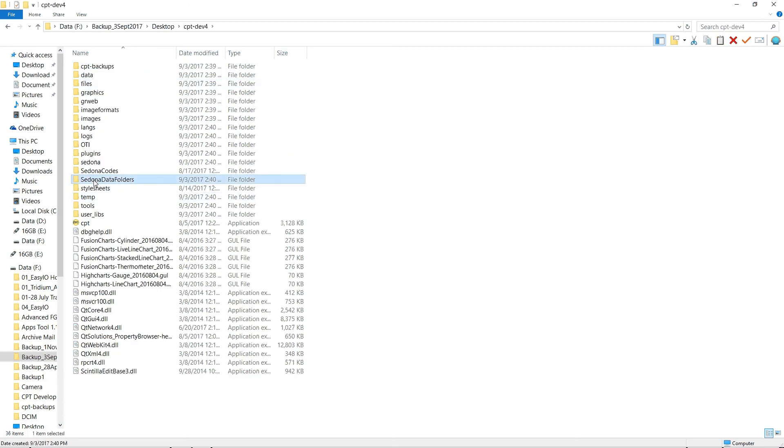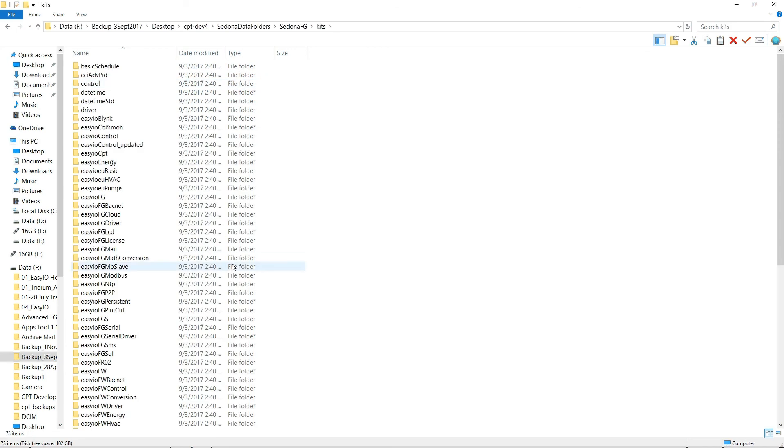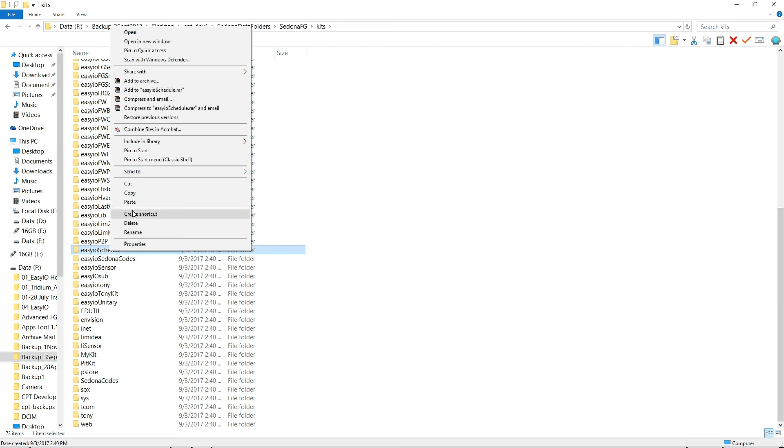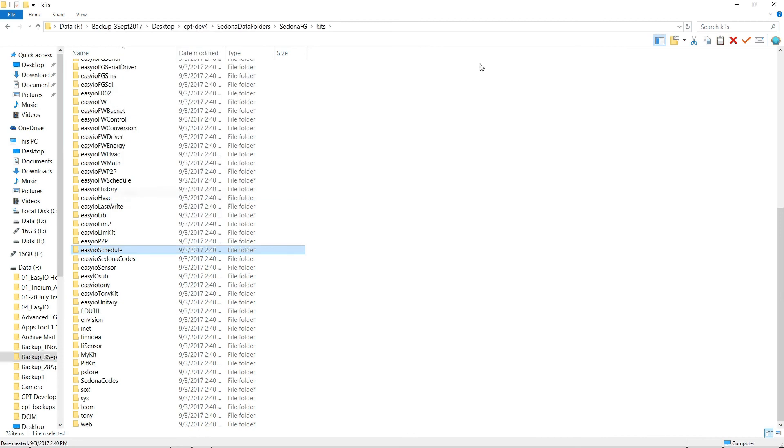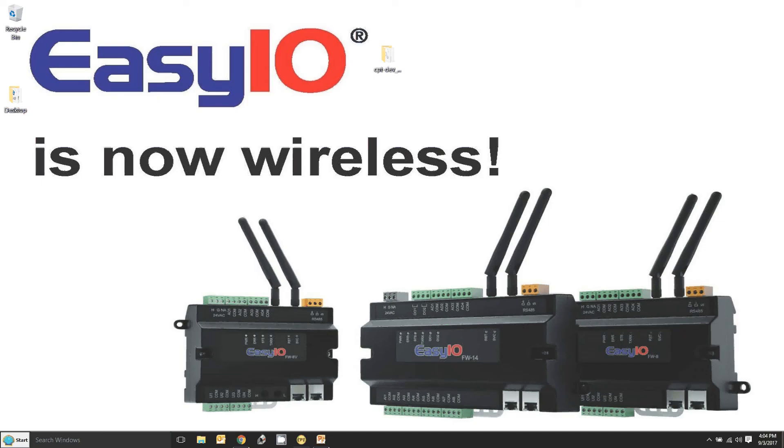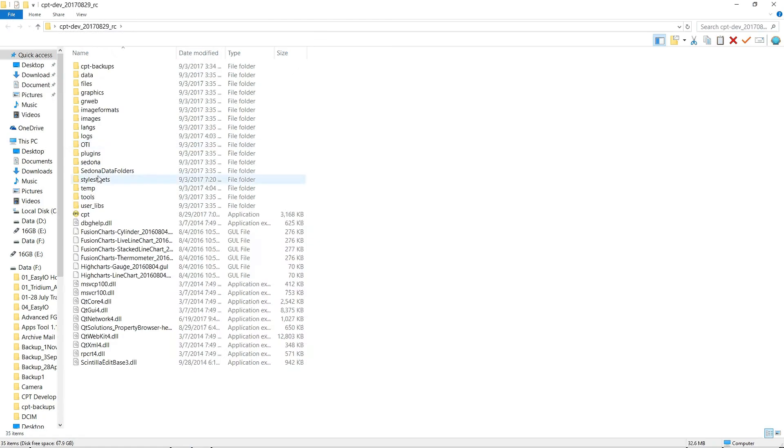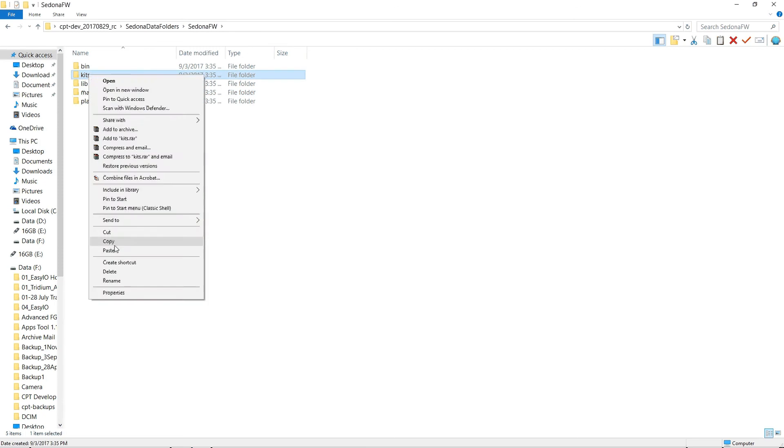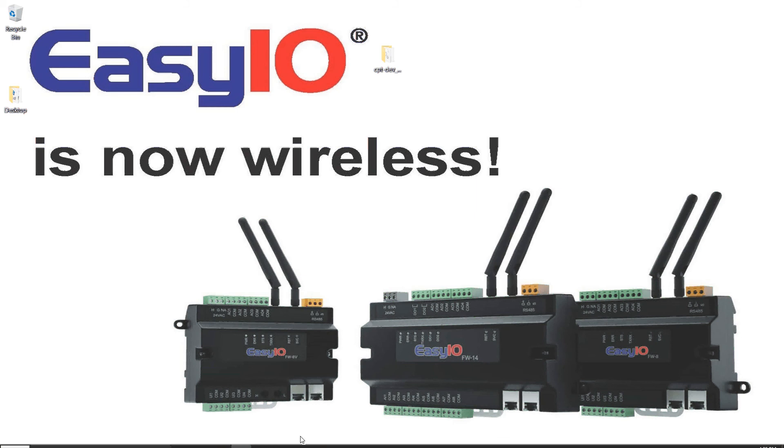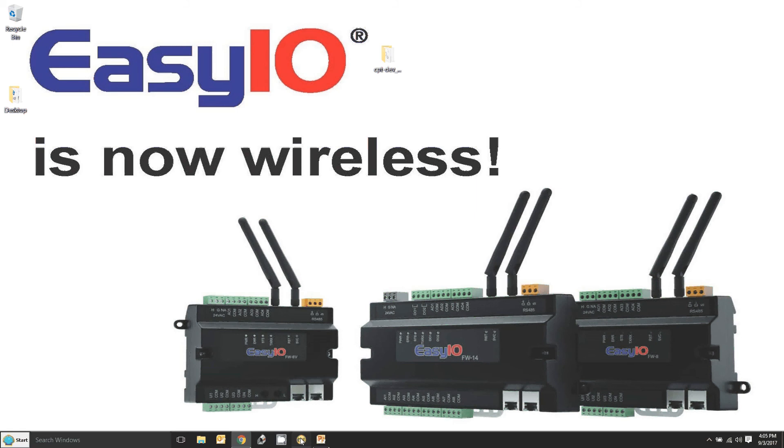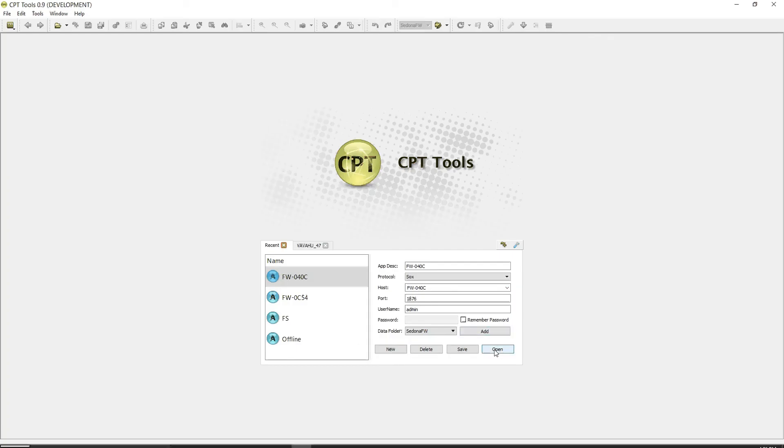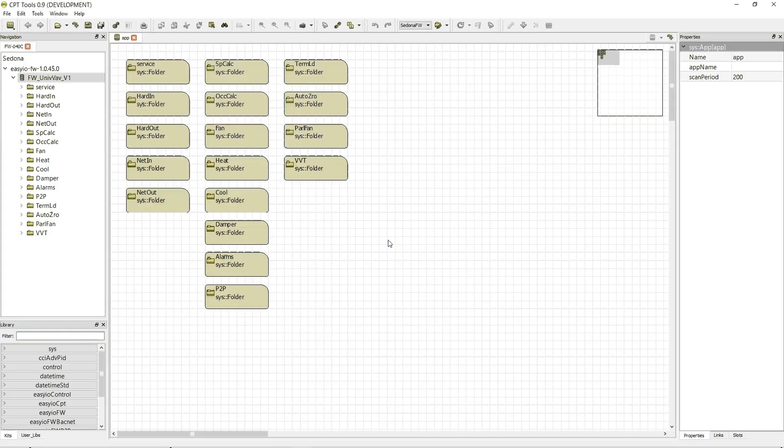So if I just go down to here. Just copy it across EasyIO schedule. It's down here. Copy. So if this ever happens to you this is what you do. Just go into my CPT which is on my desktop. Data folders. FW kits. Just paste it in there. And now when I open it we won't have any problems. I'll just do this again. Open.